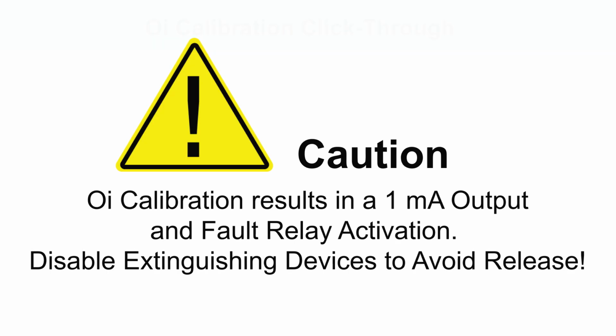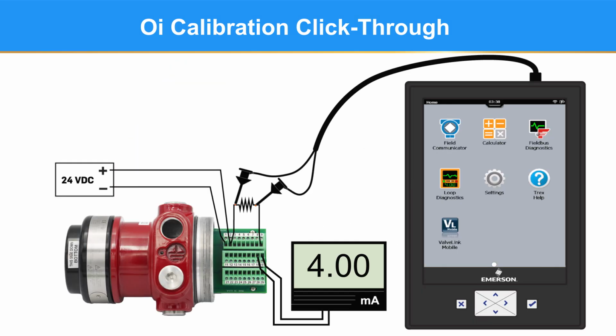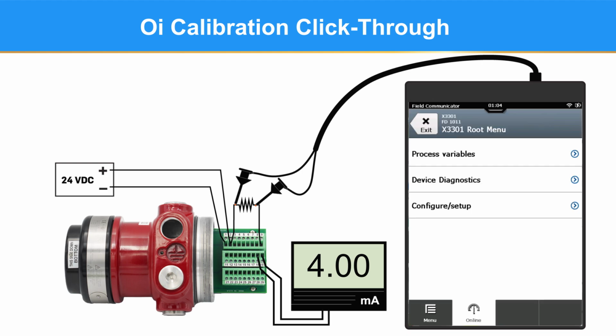Before you begin, the output of the detector will go to 1 milliamp and the fault relay will be energized during the calibration process. You must disable any extinguishing devices before starting the calibration. This drawing would be how you would set up for an OI calibration in the shop. The milliamp meter is not needed. It is simply there to show you the milliamp change during the calibration.